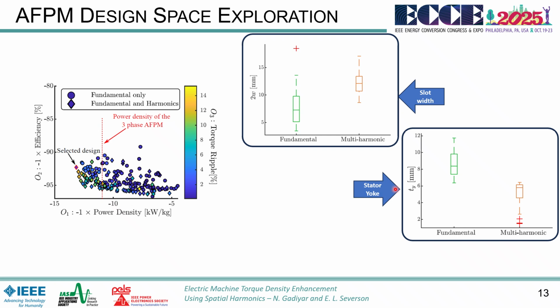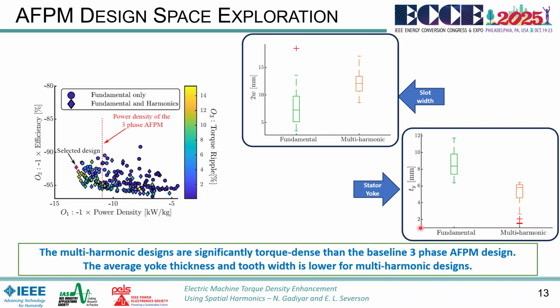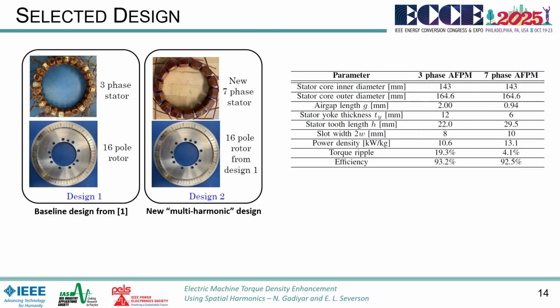And if you look at the slot width and the stator yoke, you can see that the slot width of the multi-harmonic design is significantly higher, which means the tooth width is narrower, because the stator is composed of slots and teeth. So if the slots are wider, the teeth are narrower. So again, better utilization of iron. And even if you look at the stator yoke, you can see that the yoke thickness is much thinner in the multi-harmonic design relative to the fundamental only design. So we see the same conclusions are valid here, where the average yoke thickness and the average tooth width are lower for multi-harmonic designs. So we selected the design and we fabricated a new stator.